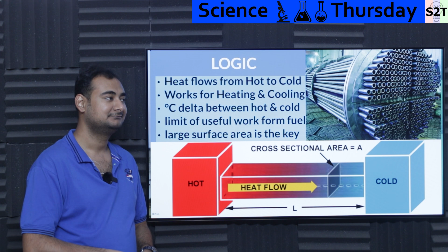That's the logic behind it. The larger the surface area, the more oomph you can transfer from A to B. This directly controls efficiency. If you don't have much temperature delta - the hot isn't that hot, the cold isn't that cold - you need a lot of surface area. You can't get away with just 1 square meter; you might need to start with 100 square meters, then go up to 5,000 square meters.